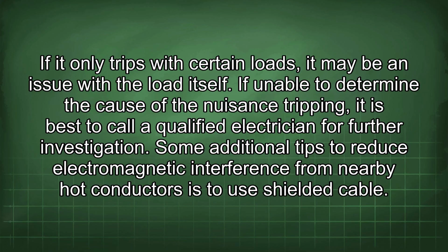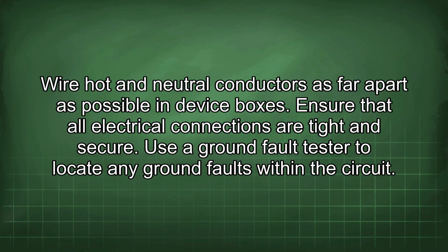Some additional tips to reduce electromagnetic interference from nearby hot conductors: use shielded cable. Wire hot and neutral conductors as far apart as possible in device boxes. Ensure that all electrical connections are tight and secure. Use a ground fault tester to locate any ground faults within the circuit.